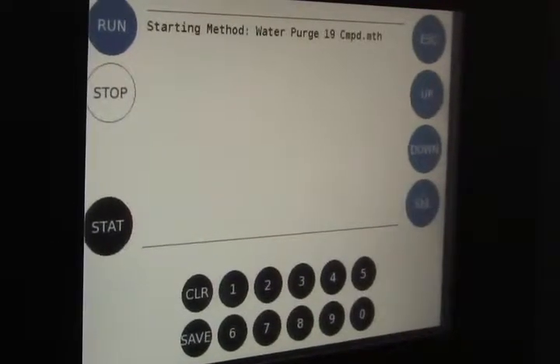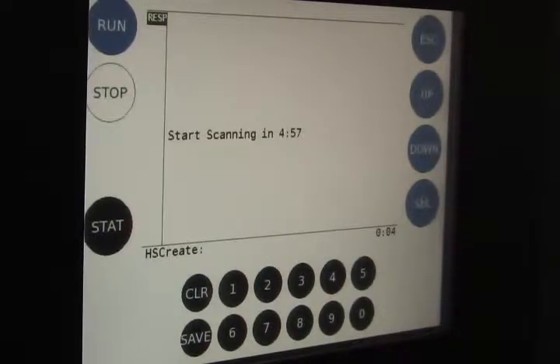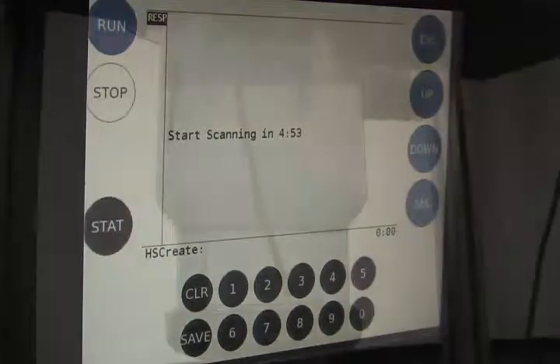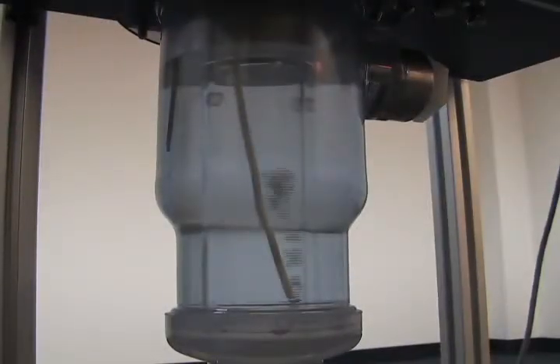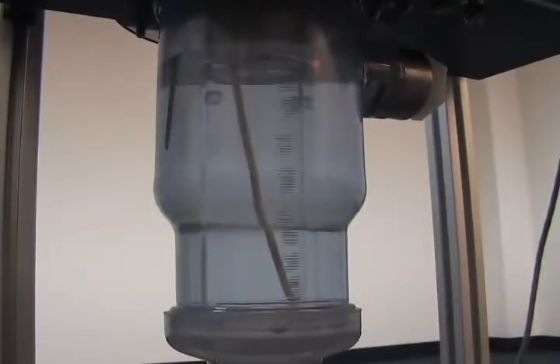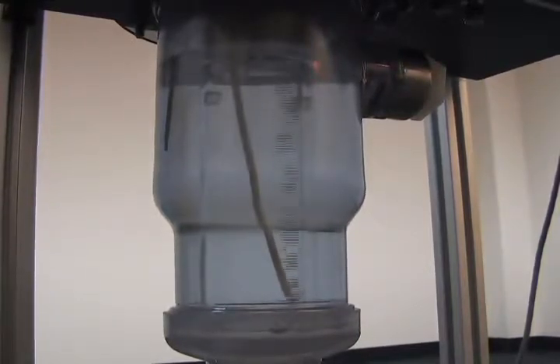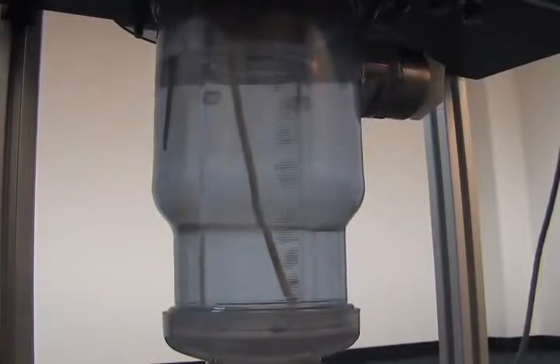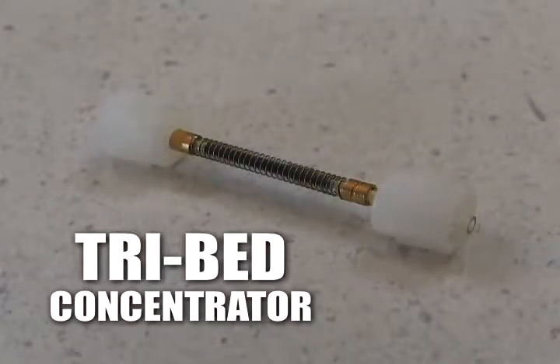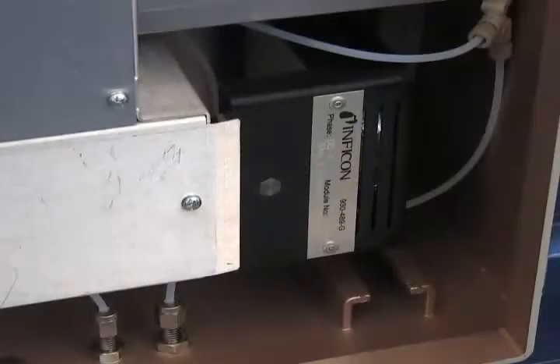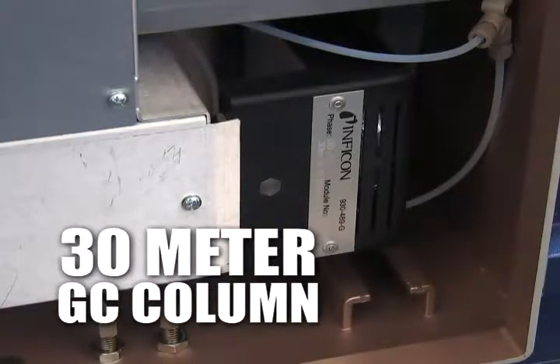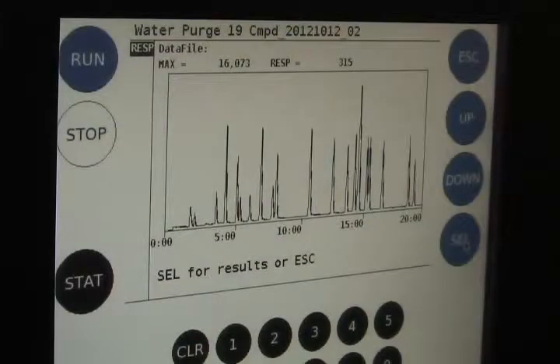The water purge method contains 19 compounds, including trihalomethanes and some EPA chemicals of concern. Argon carrier gas will flow through the water purge tube, and the bubbles produced will ascend into the headspace. The collected compounds from the headspace will be drawn into the sample pathway and become trapped onto the internal tri-bed concentrator, and then desorbed onto the 30-meter GC column. The water purge method takes approximately 20 minutes to complete.